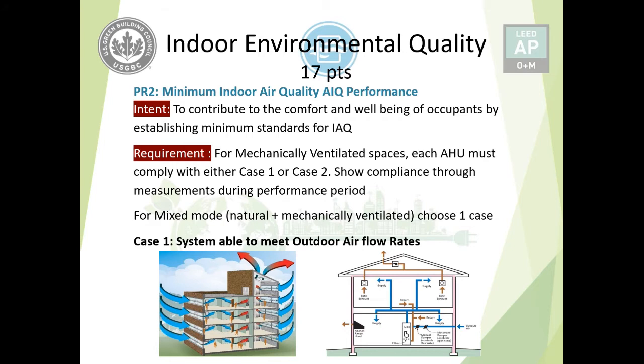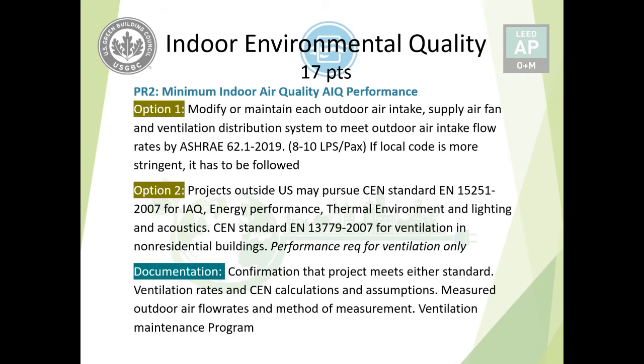For mechanically ventilated spaces, each air handling unit (AHU) must comply with either Case 1 or Case 2, with compliance shown by measurements taken during the performance period. Case 1 is that the system is able to meet outdoor airflow rates required by the standard. For Option 1, the system must comply with ASHRAE 62.1 — the American Society of Heating, Refrigeration, and Air Conditioning Engineers standard — which requires 8 to 10 liters per second per person. If the local code is more stringent, it must be followed.